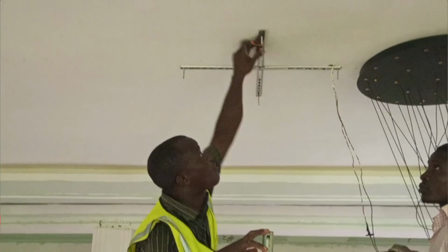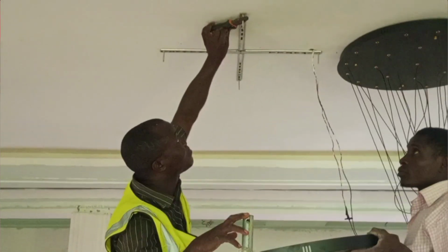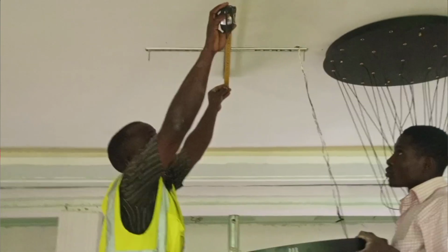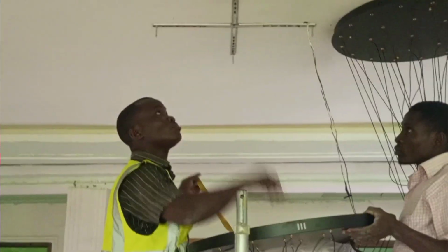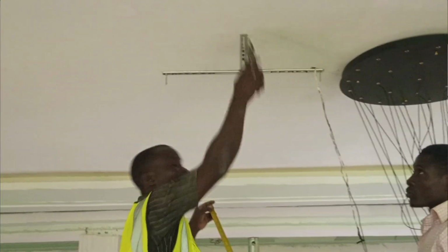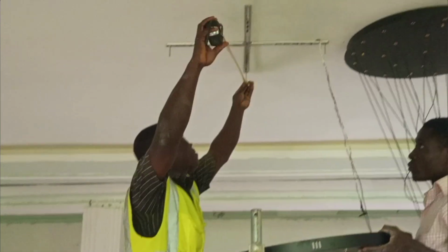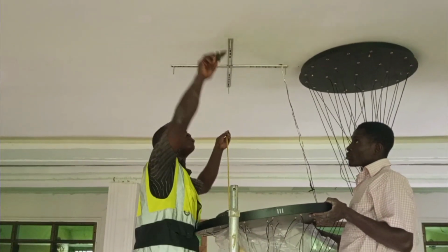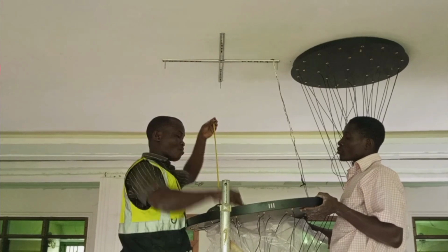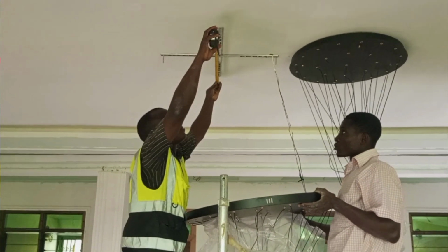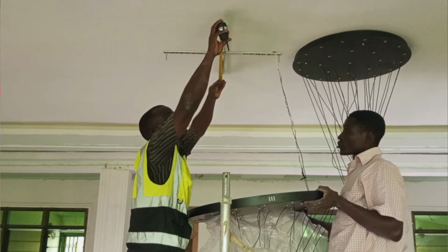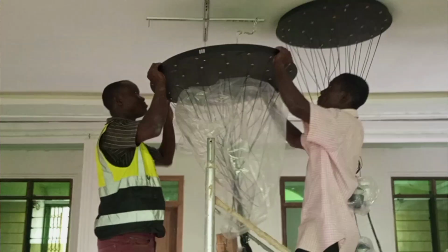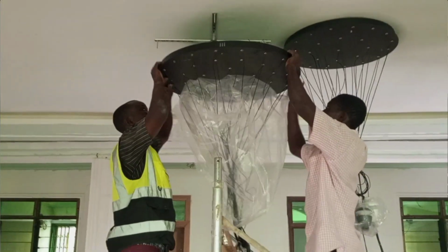So to be able to properly determine that, we would first of all need to know the amount of current that each of these lamps will require to work, and that will inform us whether we can add it to an existing lighting circuit, or we would have to create another circuit for these two, or depending on the power rating, we may even have to create separate circuits for each of these two.